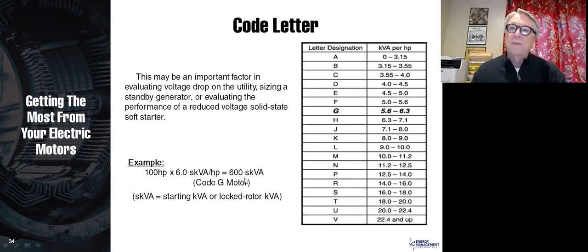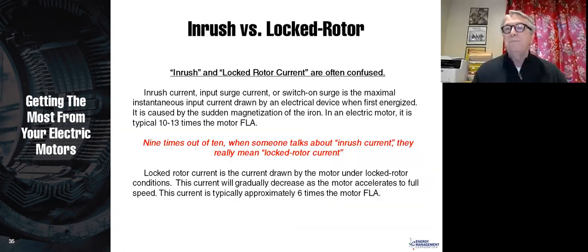But all motors are not the same. Most motors are either F or G. And so a G letter designation would say we have somewhere between 5.6 and 6.3 starting kVA per horsepower. This can be very important if you're looking at voltage drop. It's very important when sizing a generator, because generators have to start motors as well as run motors. And I've seen many, many generators sized perfectly well to run a motor. Unfortunately, they just wouldn't start the motor.